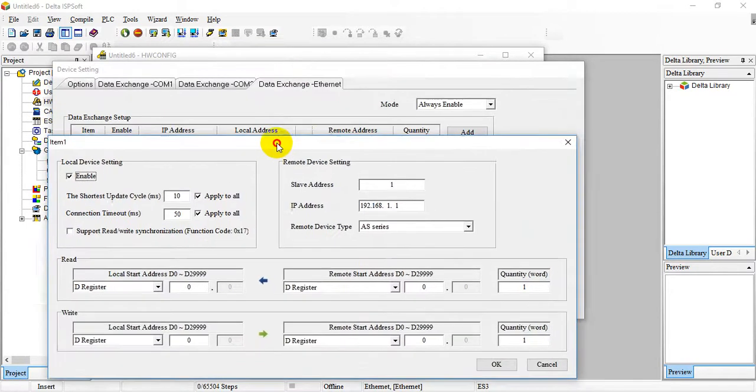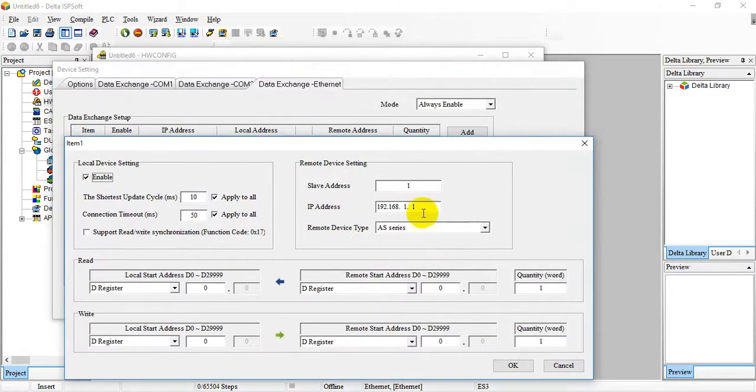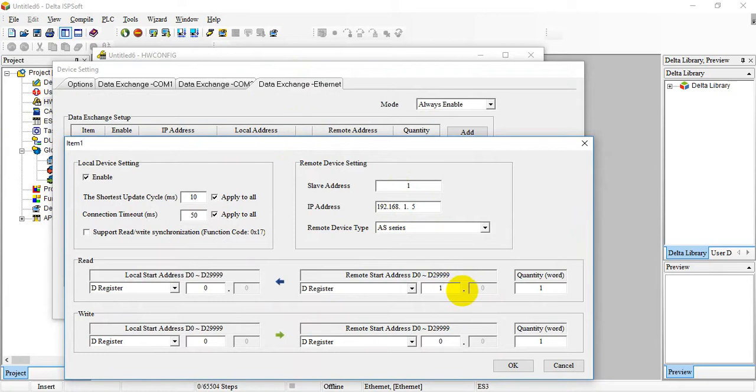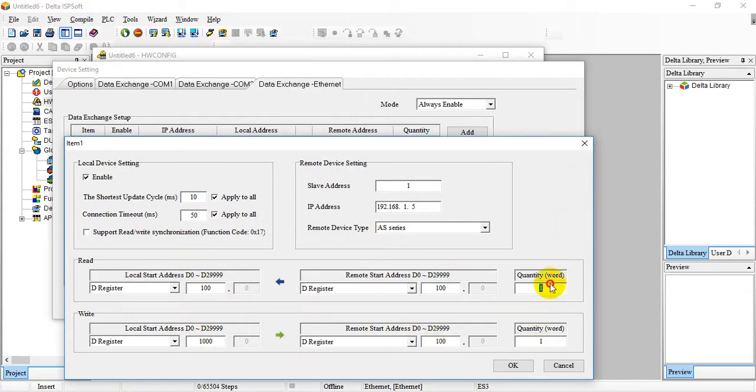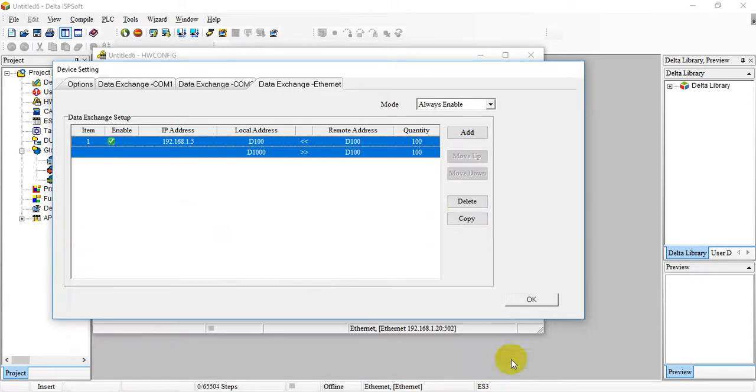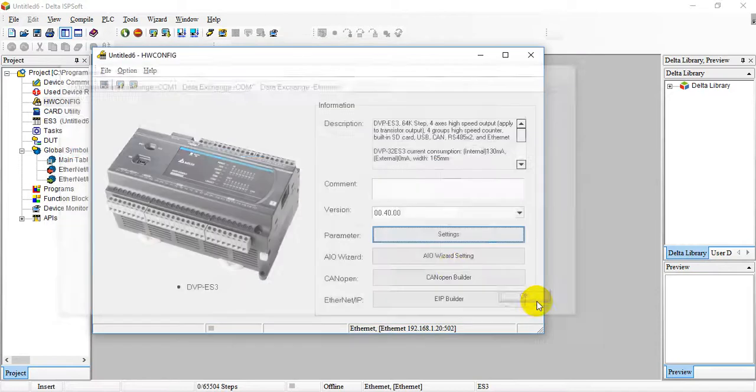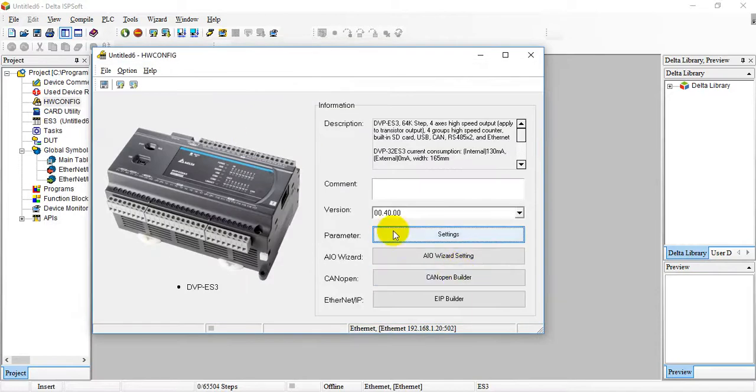Let's go over here and select enable and select Add. We select enable and change the IP address to 192.168.1.5. We can assign here start D100, and for the remote write D1000, and here we can add 100 words. After this we can download the setting.